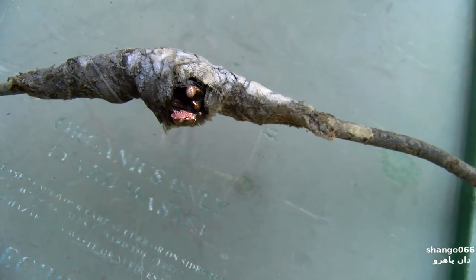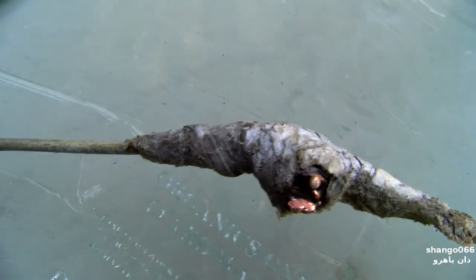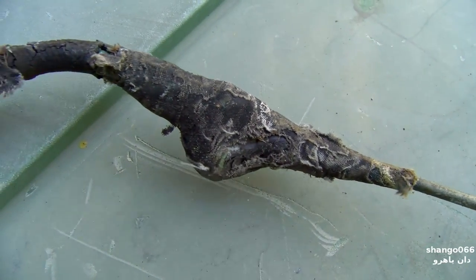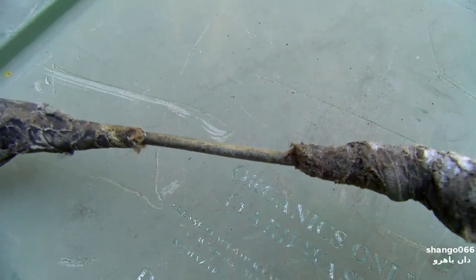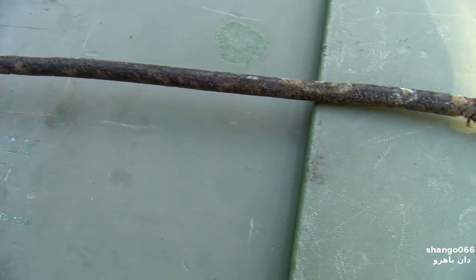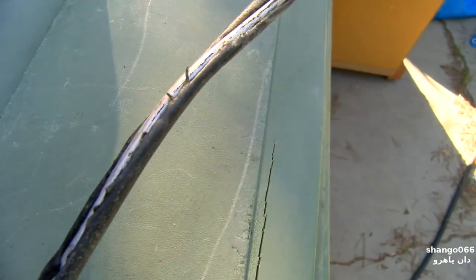Check out this point where it arced — look at that puddled copper. So here we've got tin, four gauge cloth wire, then it comes to one of those screw clamps. Then it looks like 10 gauge copper to another screw clamp, then probably 10 or 6 gauge, then over to another connector, and then to four gauge aluminum.